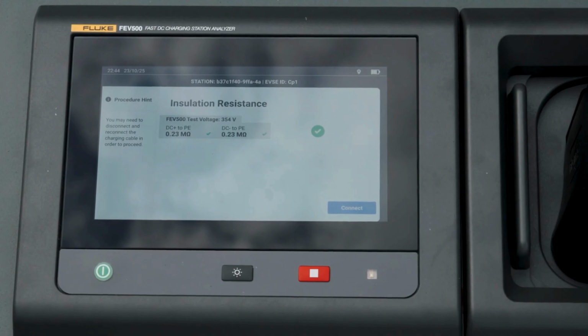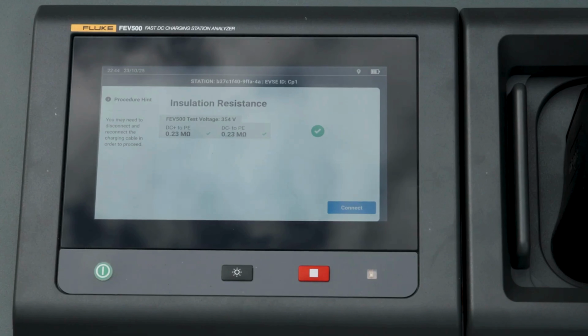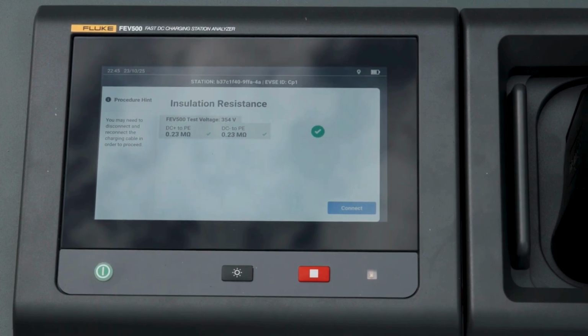One callout here, something to be mindful of: you'll want to pay attention to what the actual charging station is communicating to you on screen. So the charging station and the FEV500 aren't actually connected when we're doing the insulation resistance measurement. So now it's essentially going to reestablish communications. This oftentimes will mean you need to re-authenticate or swipe your RFID card or credit card, or use some kind of a mobile app for payment. And occasionally, depending on the charging station, some of the charging stations also like you to disconnect the CCS connector from the socket on the FEV500. So just, again, be mindful of what the charging station is saying on the actual UI or screen display, so you know exactly what it wants you to do. So I'm going to press connect.